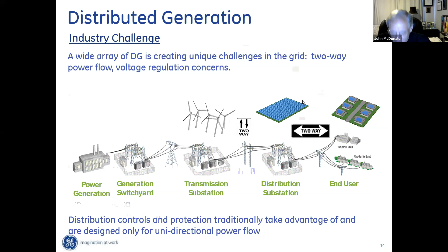When we designed the distribution part of the grid, we designed it for one-way electricity flow from source to load. And it was always that way, right? When a field worker from a utility goes out to do some work, they felt that all they had to do was open the upstream device and they had a de-energized situation and a safe working situation. That's not true anymore with the integration of distributed generation. The industry challenge now is we have two-way electricity flow, okay? Because when we start integrating distributed generation downstream of the substation, that causes two-way flow. So we can integrate renewable energy at the transmission level, distribution level, or the end user level.